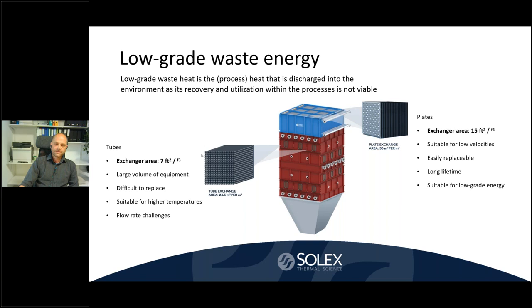For example, one heating section with typical dimensions of 11 by 11 feet and 3 feet high offers more than 4,300 square feet of heat transfer area — literally twice as much as tubes. Being able to process more product within existing space is important for plants looking to increase production capacity without significant retrofit renovations. You simply cannot install more tubes into the same area; they would have to occupy additional space mostly outside the existing plant, meaning additional investment in new buildings, platforms, product transport, and utilities distribution.